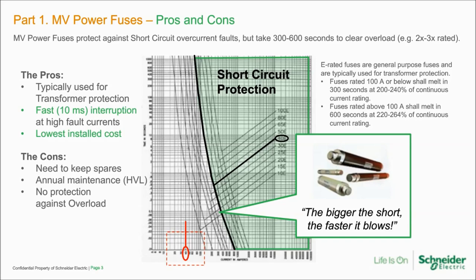This is very different from the way LV fuses are used. With my grandfather's panel fuses, if you had a 20-amp fuse, I expected it to burn out at 20 amps. With medium voltage fuses, that's just not the case — they are meant to operate differently. The bigger the short circuit, the faster it blows. The curve shows a range of operating conditions based on the amount of current the fuse sees.